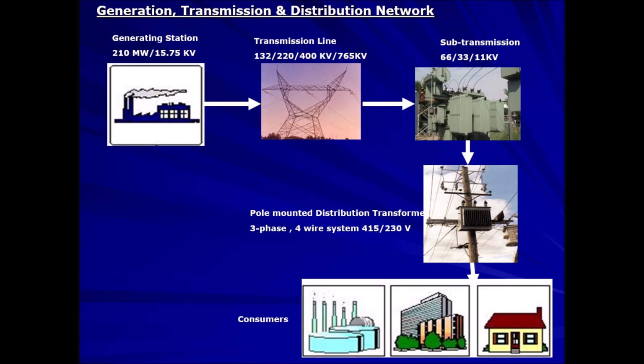This is a very simplified diagram of a power system interconnecting a generating station, transmission line and distribution system. We generate power through various sizes of generators at different voltage levels. For example, here we have taken a generator of 210 megawatt size which generates power at a voltage level of 15.75 kV with a current of about 9000 amperes.